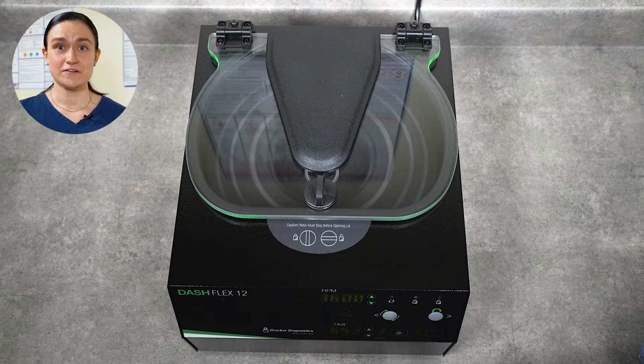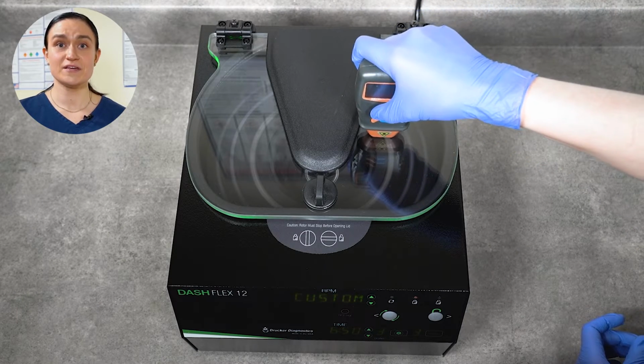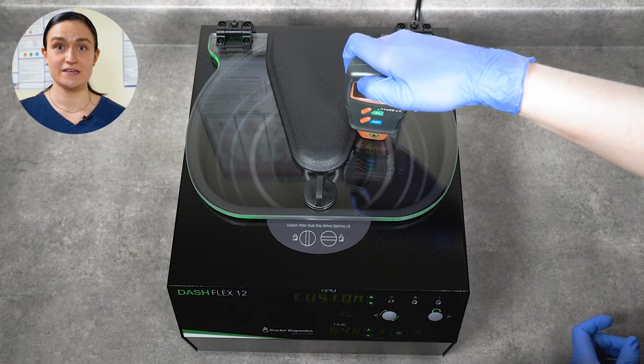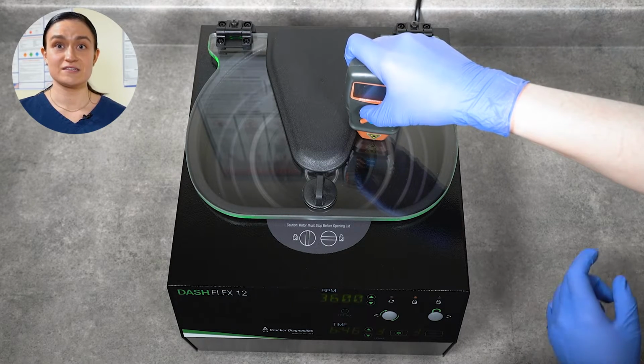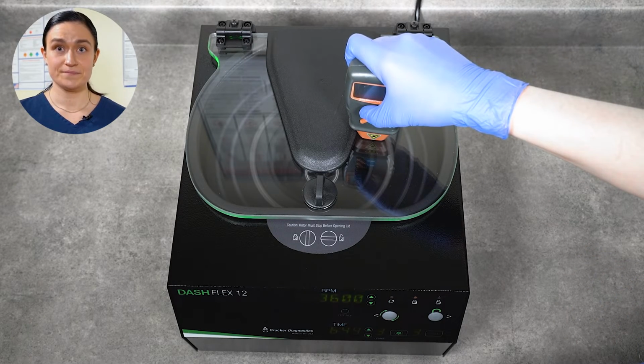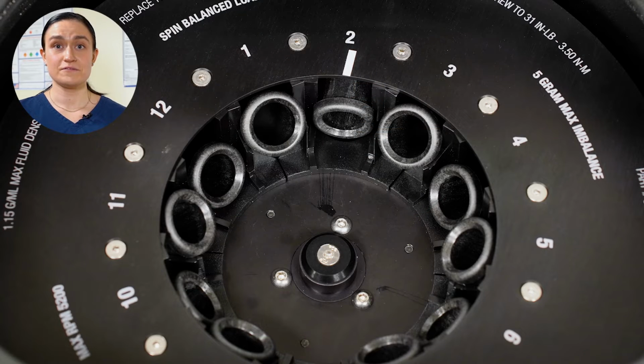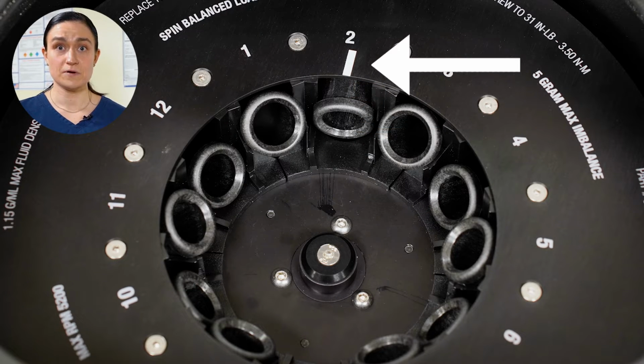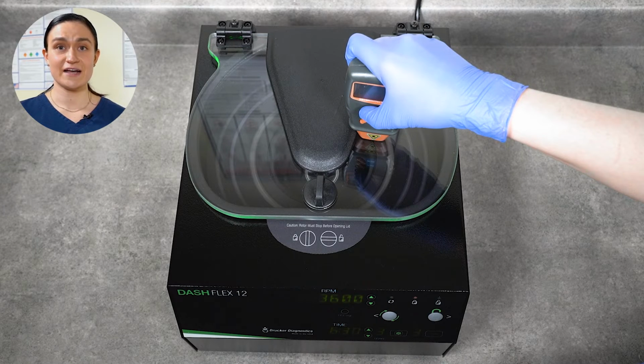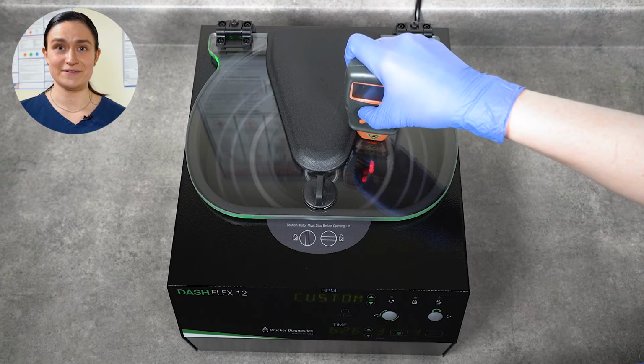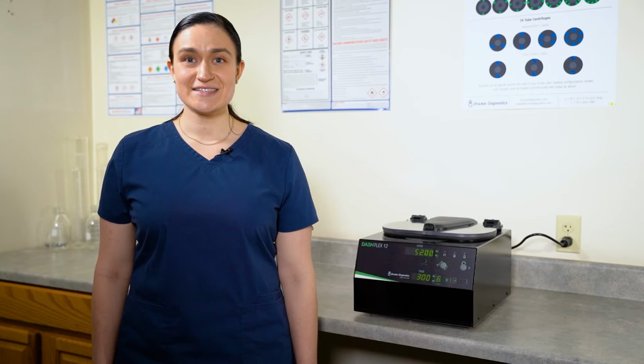Next, use your phototachometer to point down through the centrifuge lid. You'll want the area that is clear where you can see right down to the rotor. The Flex 12 rotor has a phototachometer strip mounted to it, so you won't need to put an additional strip on before you use your phototachometer. With that phototachometer pointing down through the lid, you should immediately be able to get a reading. And that's all there is to cleaning and maintaining your Flex 12.